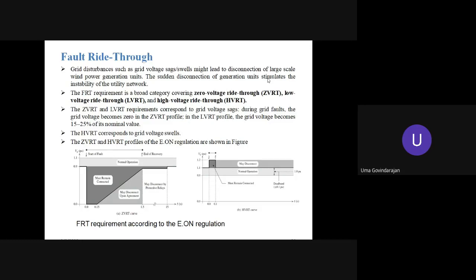The high voltage ride-through corresponds to the swell condition. Sag or swell is different from under voltage or over voltage. This is an important point. Sag is different from under voltage, and swell is also different from over voltage. So FRT, ZVRT, LVRT and HVRT are concerned with sag and swell conditions. They are not meant for under voltage or over voltage.